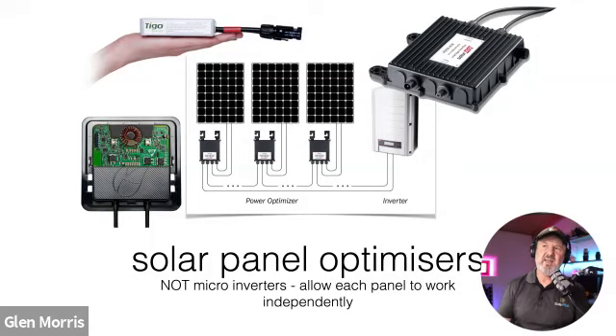So the advantage of solar panel optimizers, or what's technically called module level power electronics, MLPE, is where the solar panel itself has some device attached to it that manages its generation at a panel level, not a single inverter down at the switchboard, but each panel has a management device. Now that can be done with DC or AC. These are DC management devices, sometimes called optimizers, brands like Solar Edge, Tigo, Huawei. They all make these DC optimizers, and it means every panel works independently of every other panel to the best of its ability.